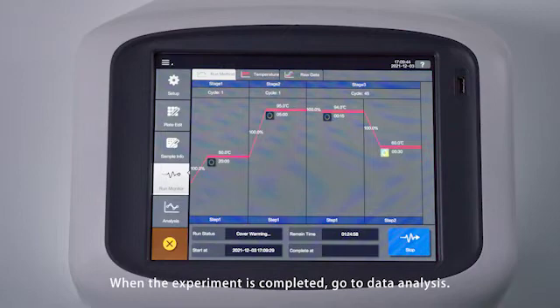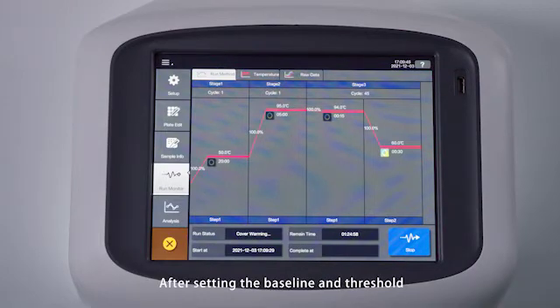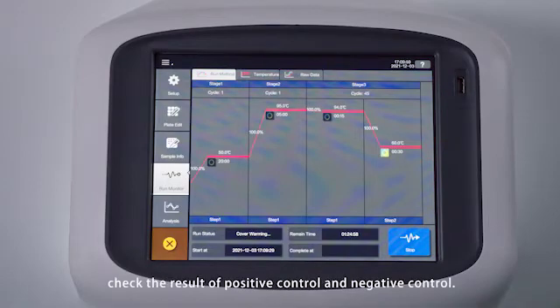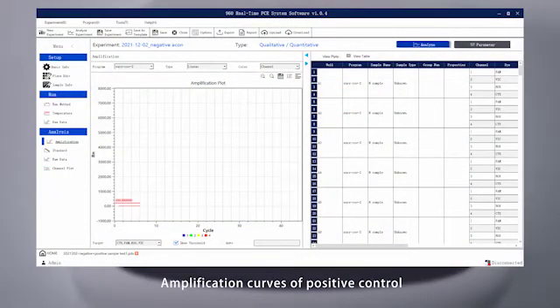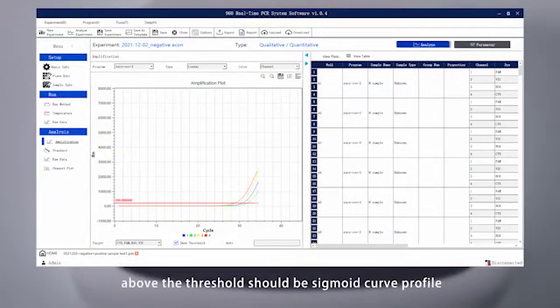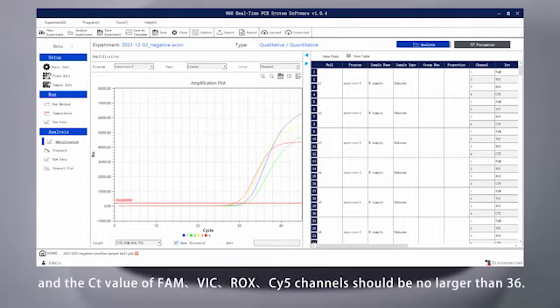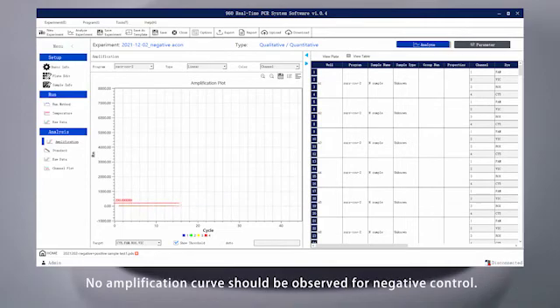When the experiment is completed, go to Data Analysis. After setting the baseline and threshold, check the result of positive control and negative control. Amplification curves of positive control above the threshold should be sigmoid curve profile, and the CT value of FAM, VIC, ROX, CY5 channels should be no larger than 36. No amplification curve should be observed for negative control.